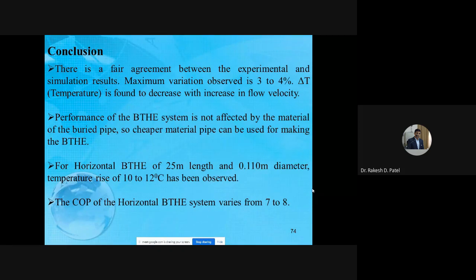Delta T, that means the temperature difference, is found to decrease with increasing flow velocity. Now, the performance of the heat exchanger is not affected by the material of the buried pipe. As per the experimental, analytical and CFD results, there is not much difference in the temperature due to the material. So a cheaper material that is easy to install can be used for making the heat exchanger. So I'm taking the PVC pipe for the heat exchanger.